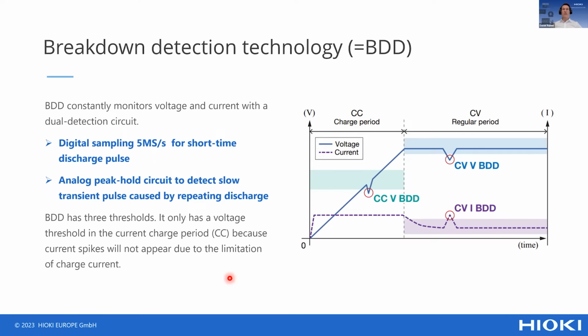So from the BT5525 on, we have a different testing procedure from what we have seen in the market so far, which is not only monitoring the voltage, but also the current. We now have two circuitries inside this device. The two circuitries first look for short-time discharge pulses at a very, very fast sampling speed, 5 megasamples per second, giving you a very clear picture and more data points, while we also have a detection circuitry for slow transient pulses.